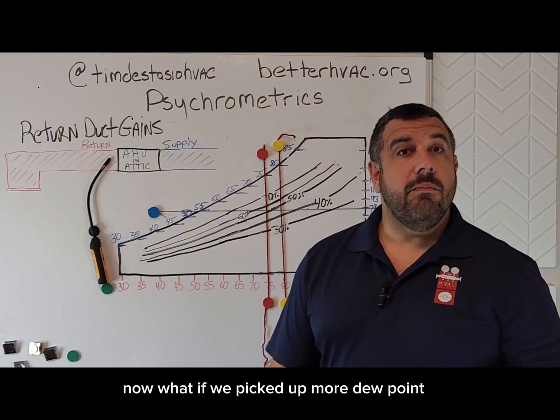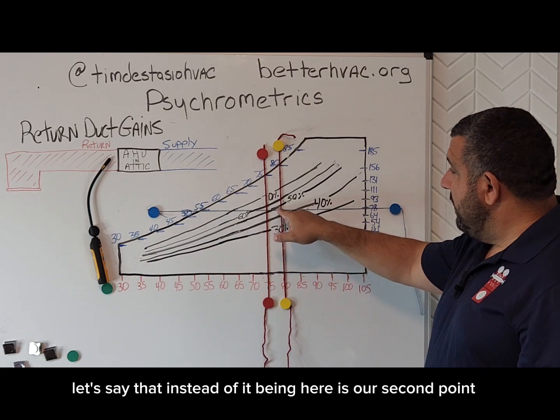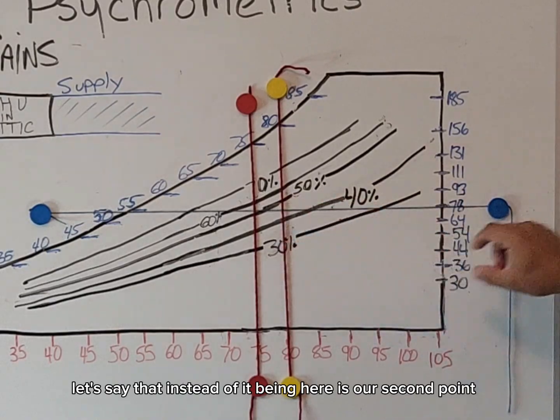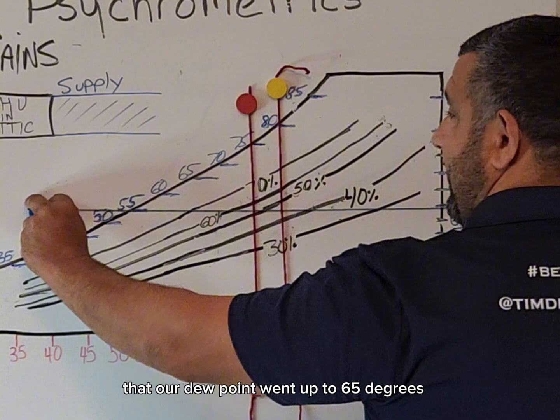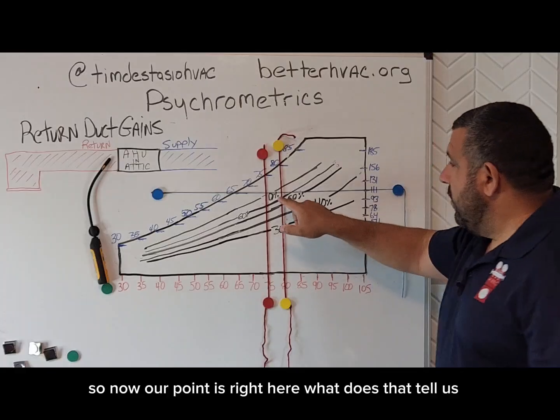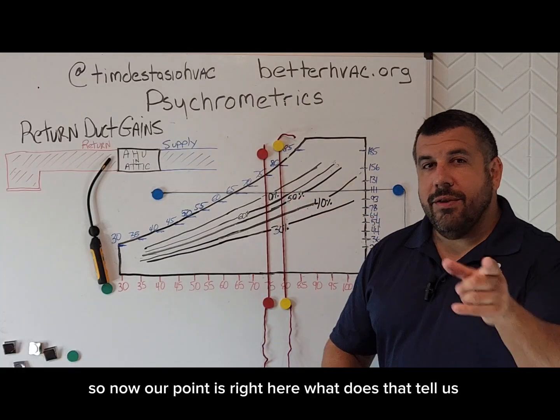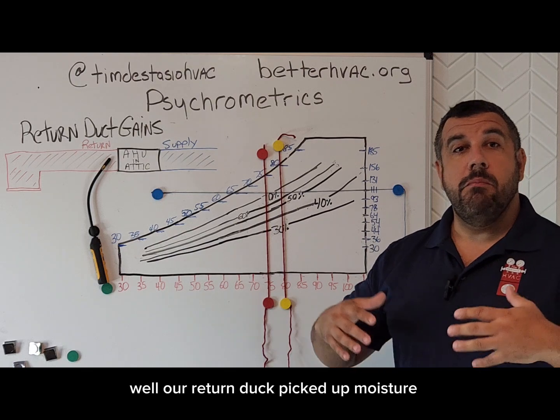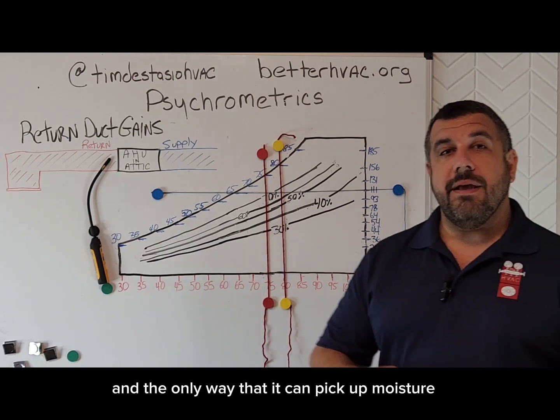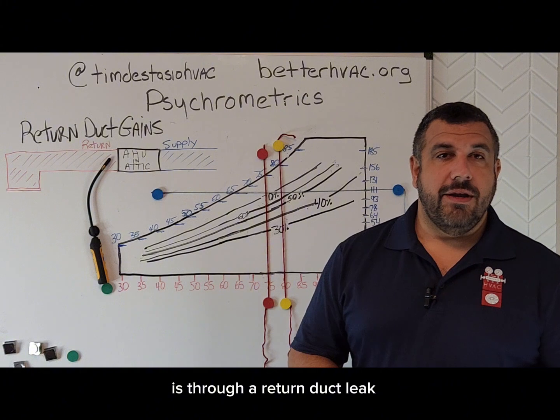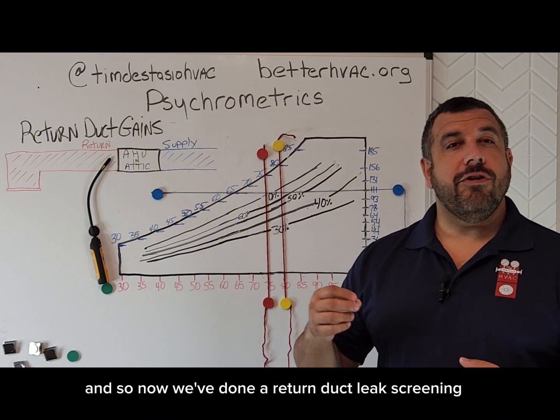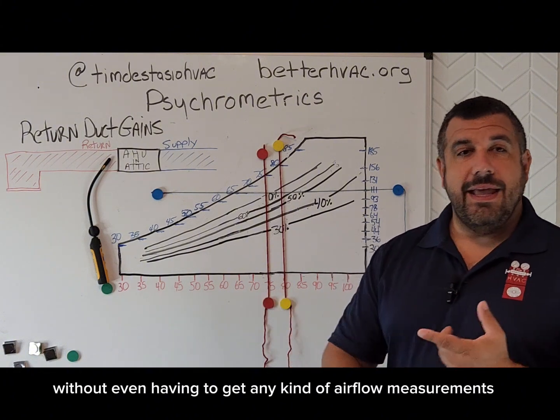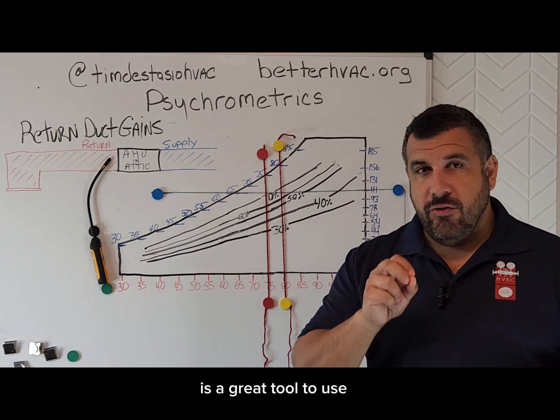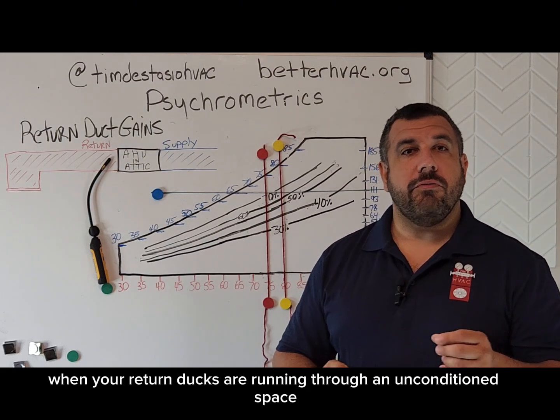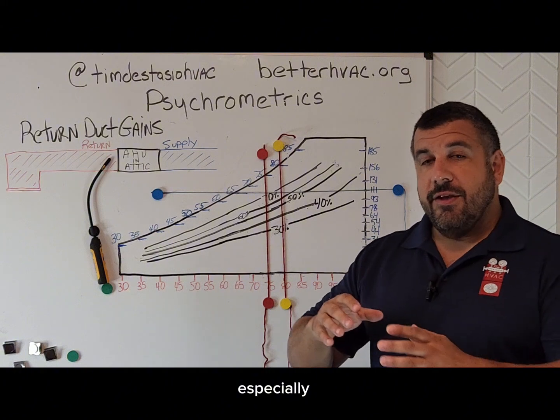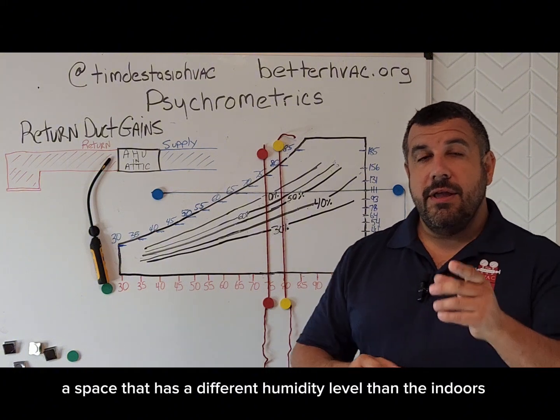Now, what if we picked up more dew point? Let's say that instead of it being here is our second point, that our dew point went up to 65 degrees. So now our point is right here. What does that tell us? Well, our return duct picked up moisture, and the only way that it can pick up moisture is through a return duct leak. And so now we've done a return duct leak screening without even having to get any kind of airflow measurements. It is a great tool to use when your return ducts are running through an unconditioned space, especially a space that has a different humidity level than the indoors.